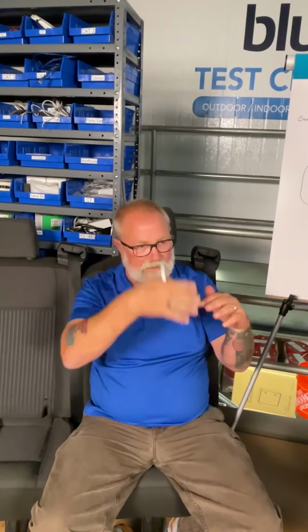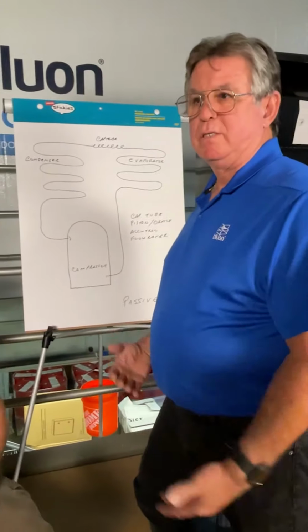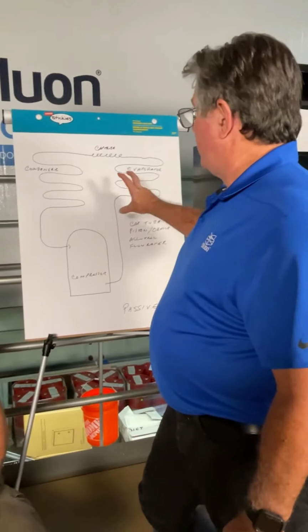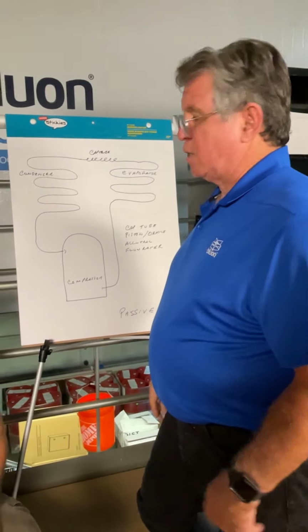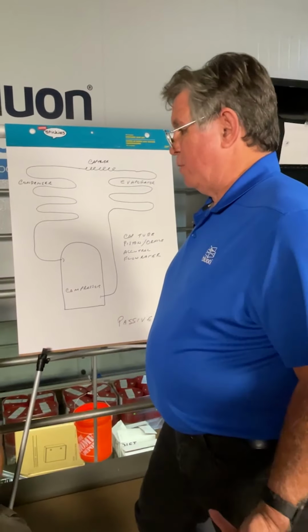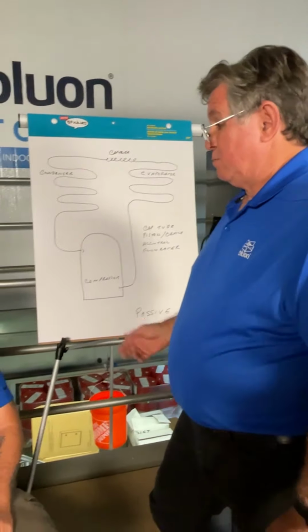It's a safety built in that even if you do put your numbers in and your numbers are off the benchmark, Mike was talking about the crossing left to right, your X's and Y's. If you're off that chart, then you will look and you'll see that 5 didn't change, and that's because you're off the chart. If you put your numbers in and it still shows what you saw when you opened up the app, it's only just the safety factor. So this gives you a way to do things, but like you can see, we have basically a weigh-in charge. It's a critical charge. So when we have no more refrigerant in there, that's all the system can do.